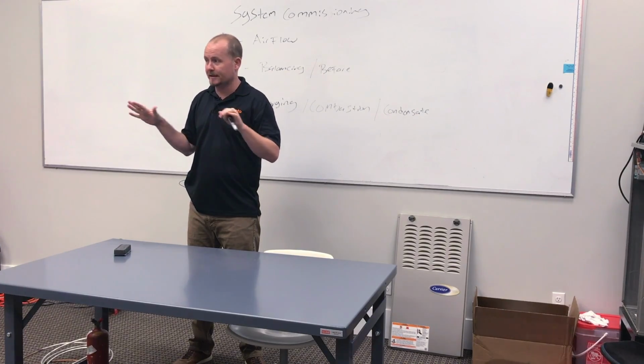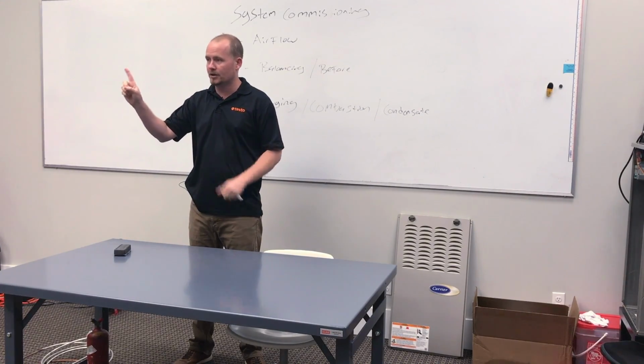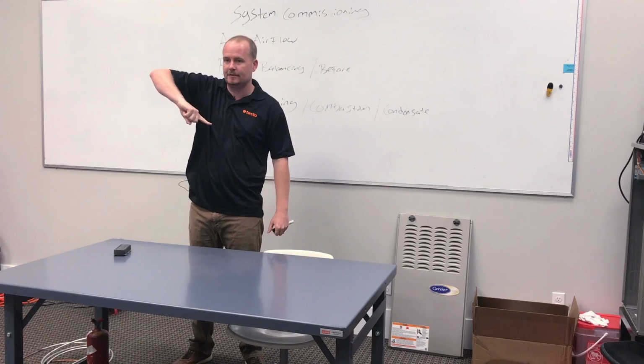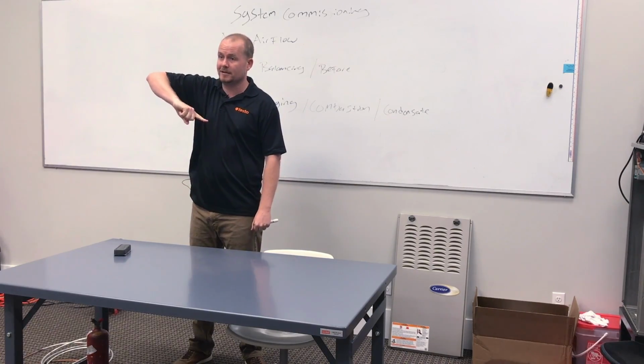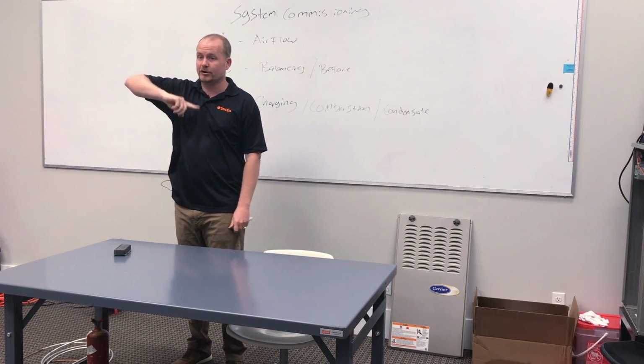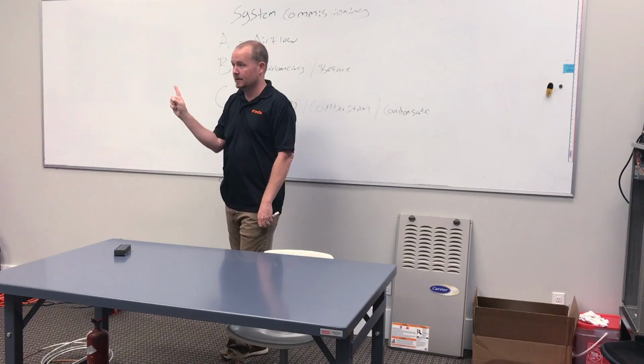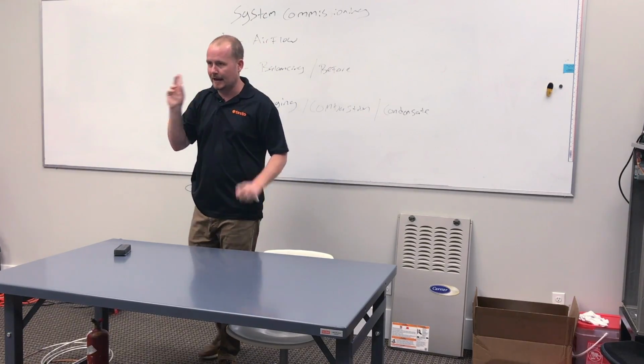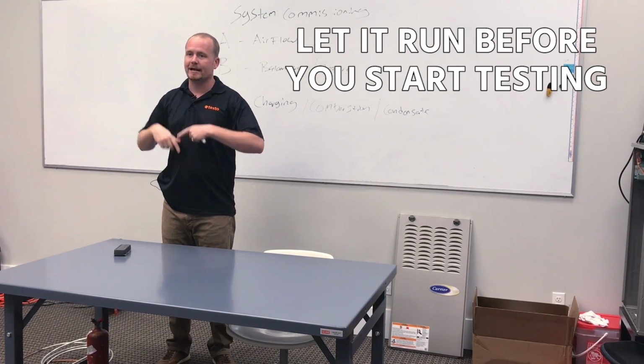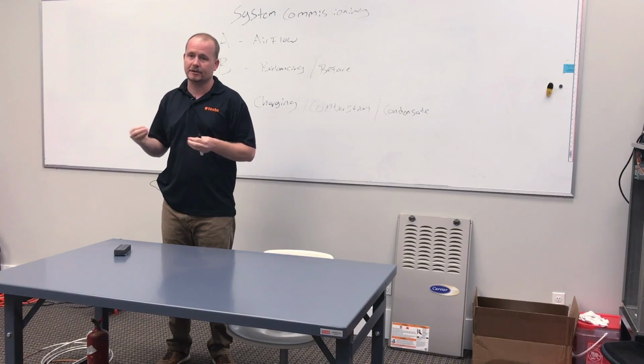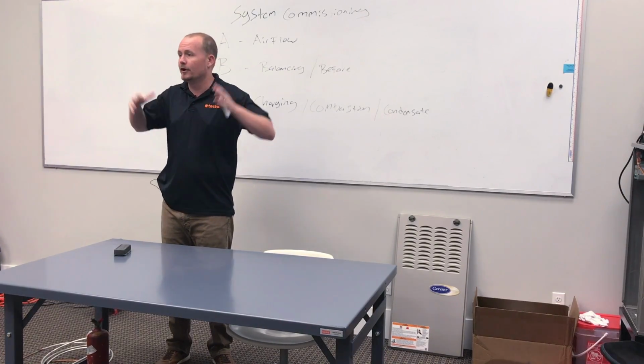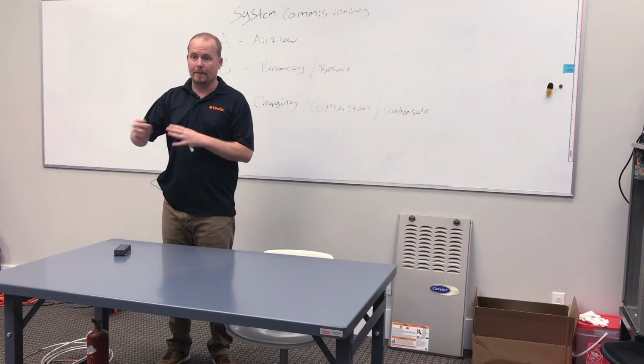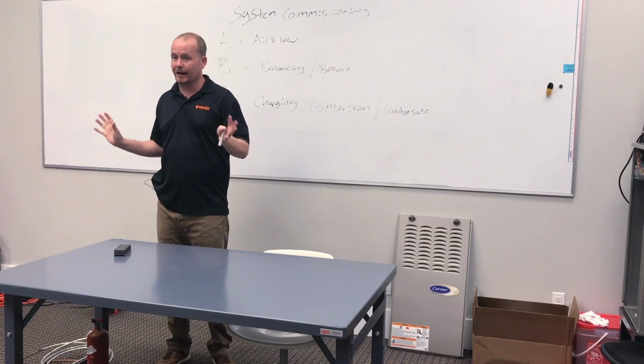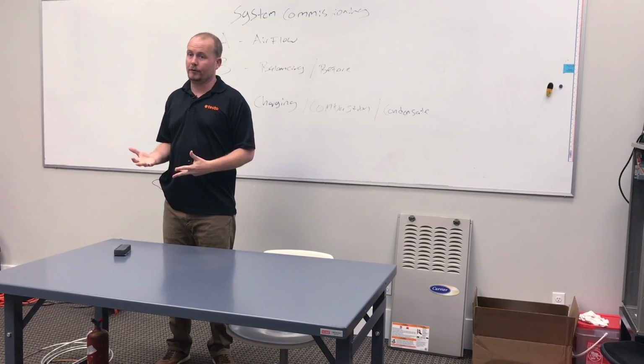Don't start focusing on your gauges right away. Now you do want to watch to make sure your suction gauge doesn't dive down to 0 or something. But what you don't do is like what we talked about the other day, where you start jack and charging it before it's stabilized. So now, once you've made sure everything sounds okay, you've got your airflows, now you let it run a little while. Because it's going to be tough to test a system until it's run 15 to 20 minutes. 30 is even better. You can clean up, you can start doing paperwork, whatever else you've got to do, but you want to let that thing run before you start doing testing.